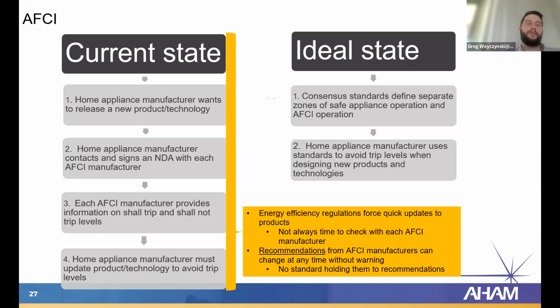The worst part about that is that it's not defined in the UL standard. These are just recommendations from AFCI manufacturers. Those can change all the time. So if a home appliance manufacturer contacts an AFCI manufacturer and we get those trip thresholds, they could change a day later and still be compliant with the UL standard. So we're working on updating the UL AFCI standard.